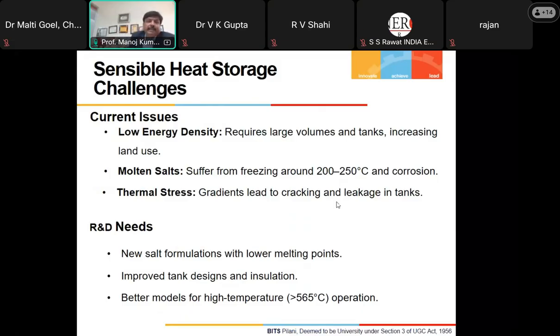So the R&D focus here is new salt formulations with lower melting points, because once the molten salt freezes, you have to heat it—either through steam jacketing or electric heating—to melt it before running the plant. Second is improved tank design and insulation to minimize losses and avoid cracking, along with better models for high temperature applications.